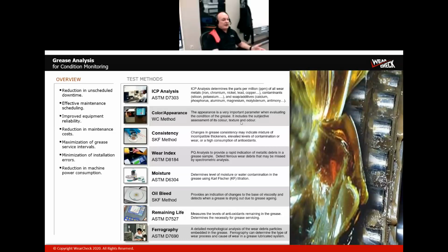So we're not trying to assess greases for their anticipated performance. We're looking at greases in operation and assessing the condition of that equipment. We're looking for contamination. We're looking at the grease's condition for continued use. And a lot of these end up being more root cause things.